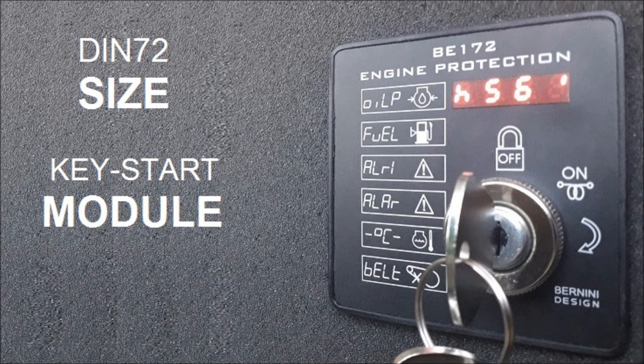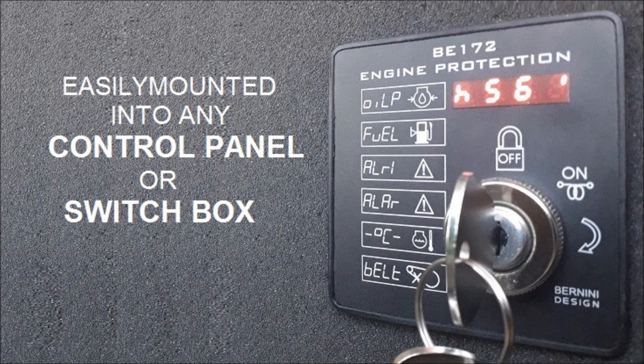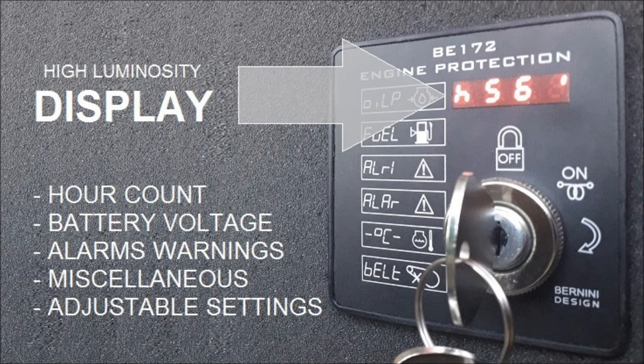The BE172 is a compact key start and protection module contained in a 72 by 72 millimeter size steel box. It features a high brightness white solid state display capable of operating between minus 30 up to plus 70 degrees Celsius. The display indicates battery voltage, hour count, adjustable settings, alarms, warnings, and miscellaneous information.